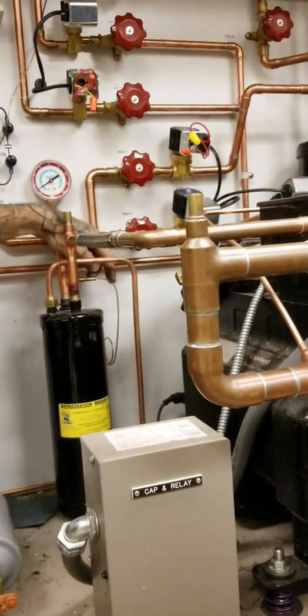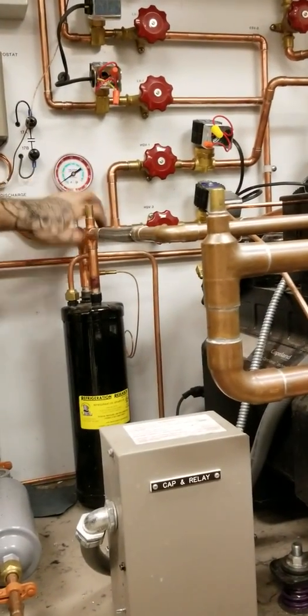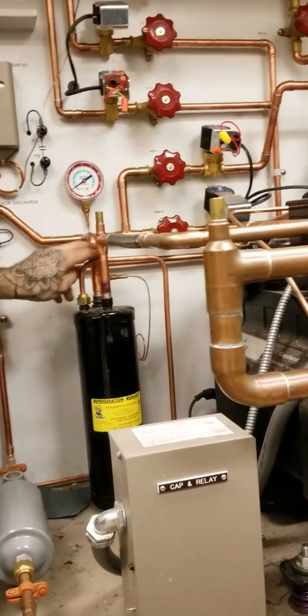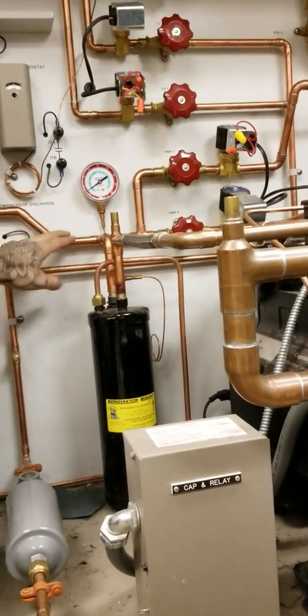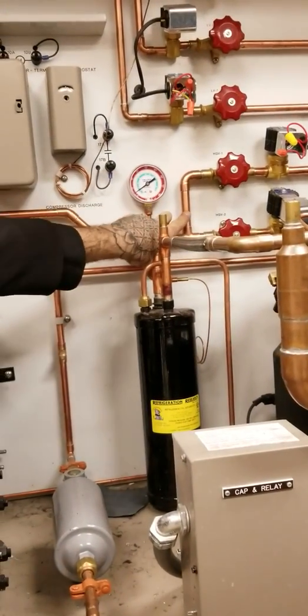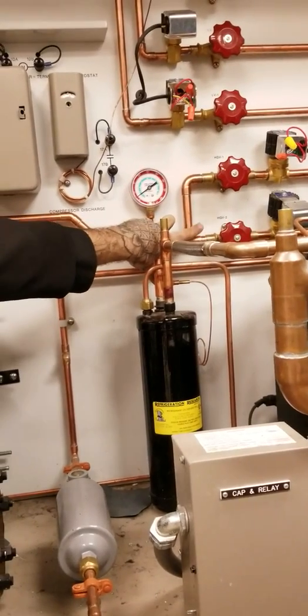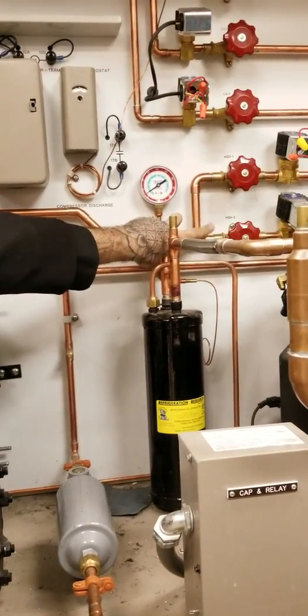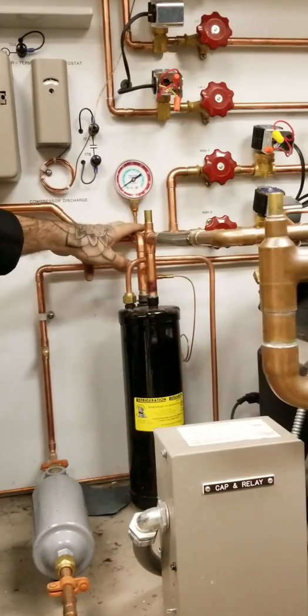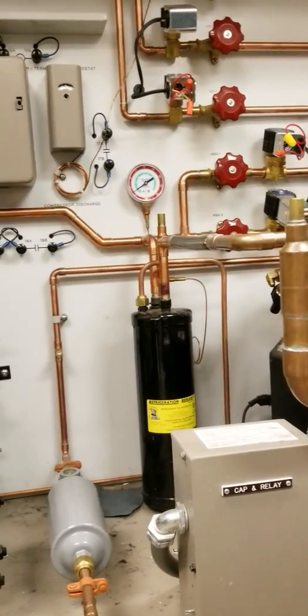Then you have your pressure tap right here. That's where our gauge is tapped in so you can see the pressure. Our hot gas leaves through here and it tees off. It could go to our hot gas solenoid valves, which are going to control when we need to defrost. I'll get back to that when we come through. Let's just follow it as the hot gas comes through.